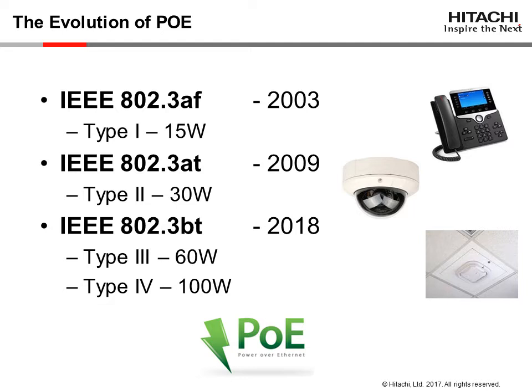In early 2018, 802.3BT will introduce two new power levels: Type 3 for 60 watts, and Type 4 for 100 watts. This will significantly increase the type of device that will utilize PoE. What started out as an option for powering phones will now power cameras, wireless access points, and even entire building lighting systems.